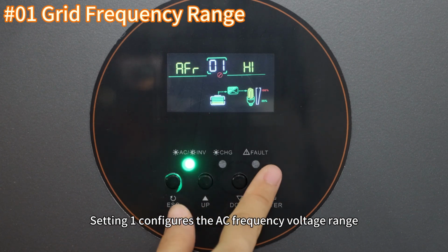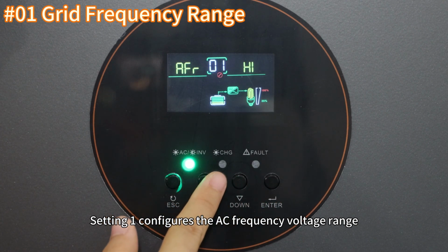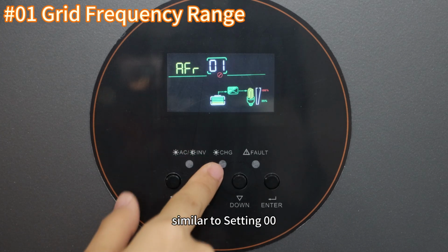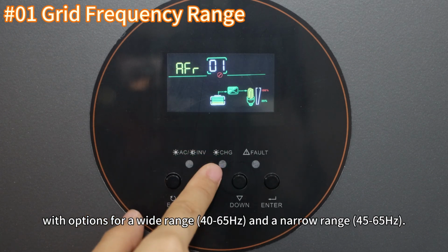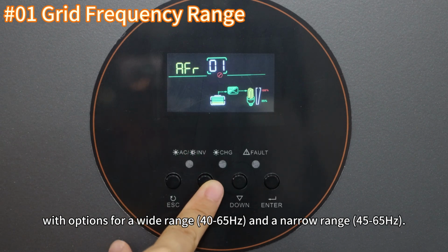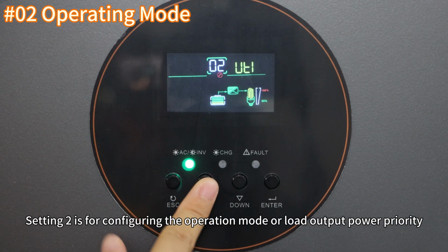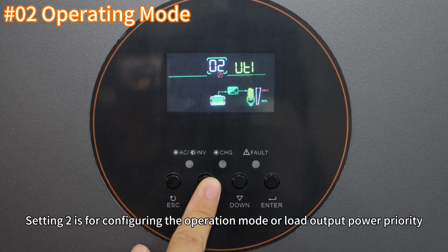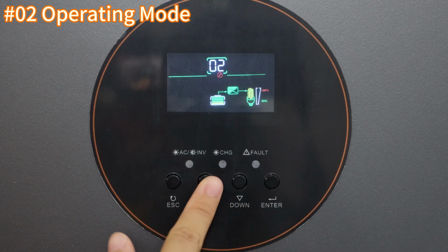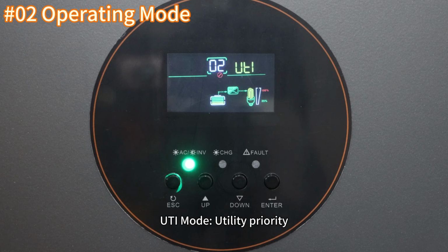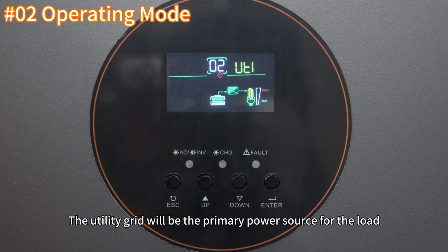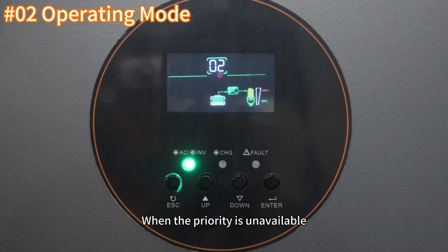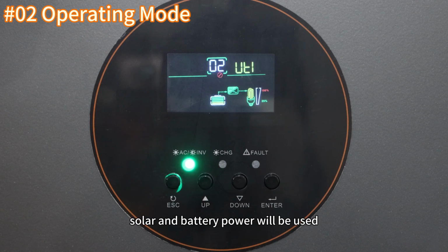Setting 1 configures the AC frequency range, similar to setting 0, with options for a wide range and a narrow range. Setting 2 is for configuring the operation mode, or output power priority. UTI mode, utility priority. The utility will be the primary power source for the load. When the utility is unavailable, solar and battery power will be used.